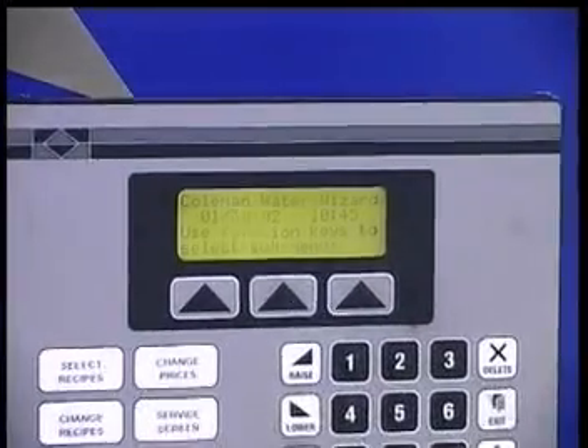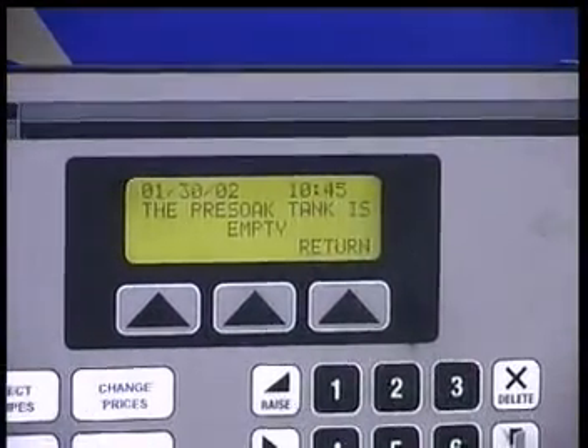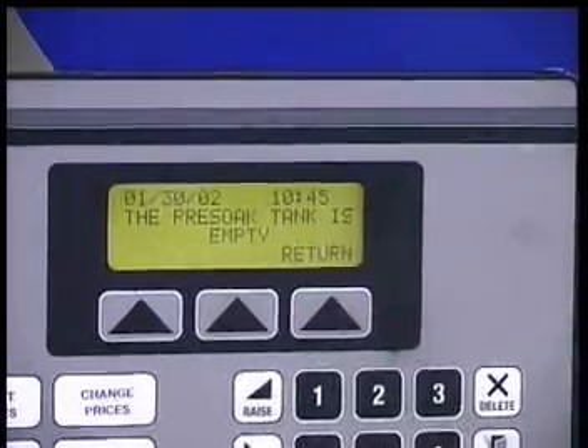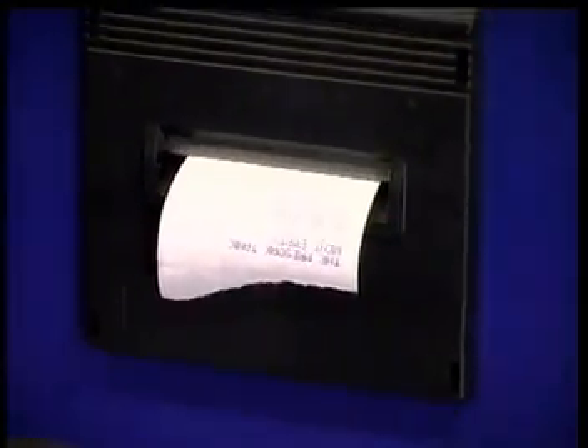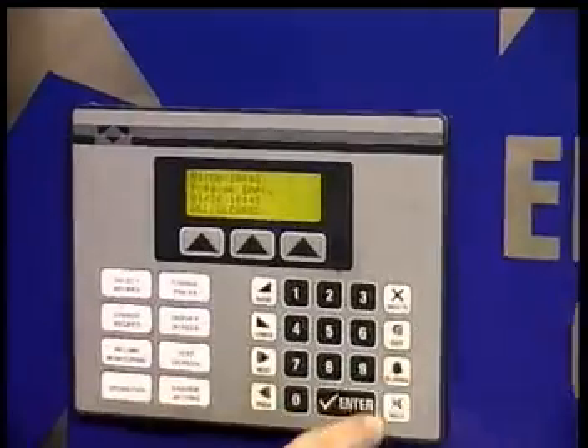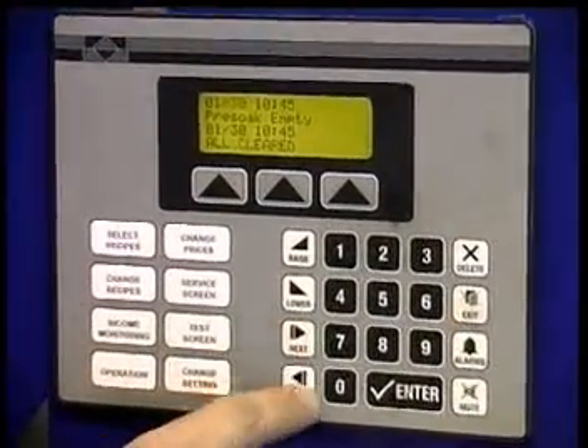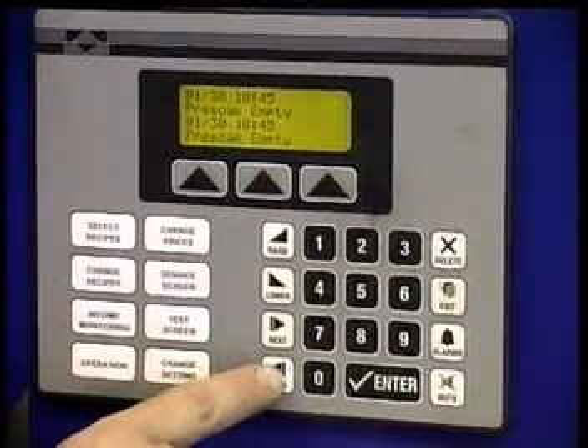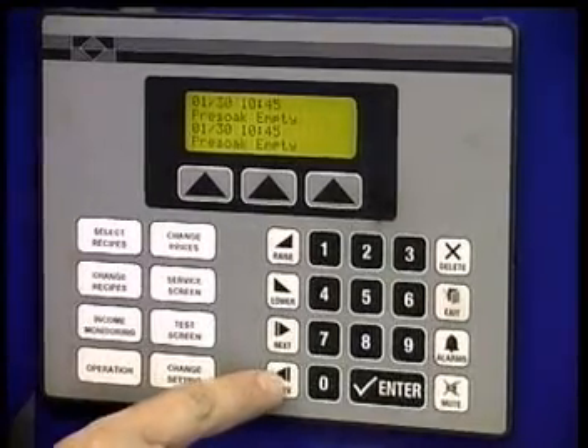In a variety of fault conditions, the Water Wizard will issue an error code indicating the type of fault, the time and date, and the location. They will automatically appear on the operator interface panel and will print out if a printer is available. The system will store the last 10 faults for review at any time. Push the alarm button on the interface panel for a list. Push the next button to scroll through them.